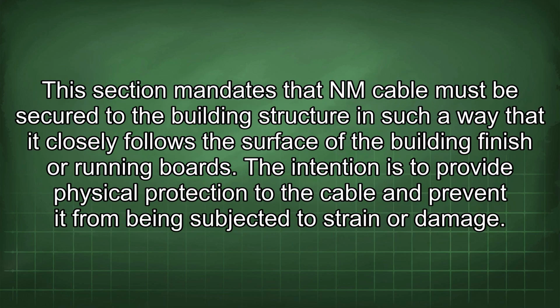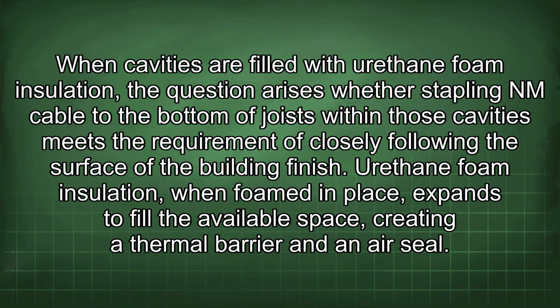This section mandates that NM cable must be secured to the building structure in such a way that it closely follows the surface of the building finish or running boards. The intention is to provide physical protection to the cable and prevent it from being subjected to strain or damage. When cavities are filled with urethane foam insulation, the question arises whether stapling NM cable to the bottom of joists within those cavities meets the requirement of closely following the surface of the building finish.